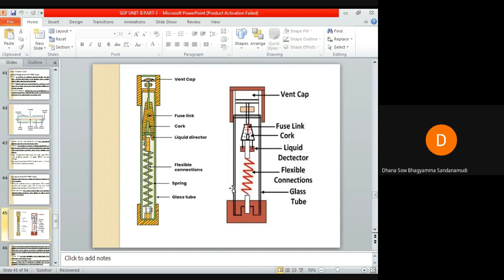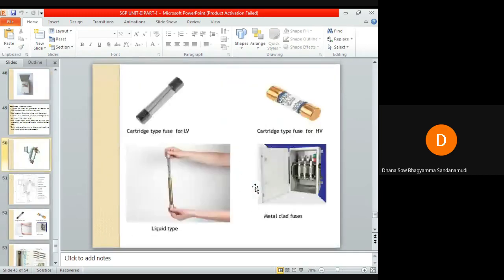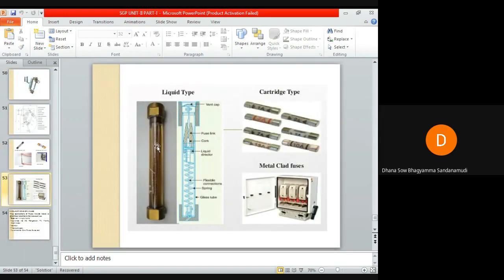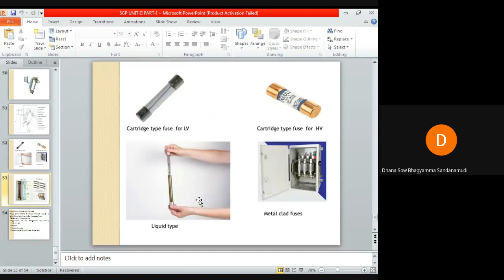6100 amperes. These liquid type HVHRC fuses consist of a glass tube filled with carbon tetrachloride solution. You can see the glass tube in the image here. This is the glass tube. I have one more image. This glass tube is filled with carbon tetrachloride solution and sealed at both ends with brass caps.